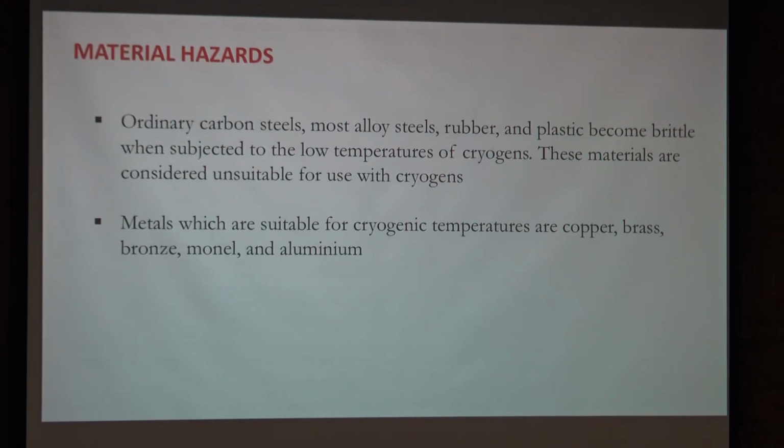Then, material hazards. That's a danger that is maybe not the biggest danger, but should be kept in mind. Ordinary materials, steel, definitely rubber and plastic, become brittle when subjected to low temperatures. At this point, when their material properties change, hazards can arise, for example, from using rubber pipe that freezes and then essentially shatters from cold liquids.